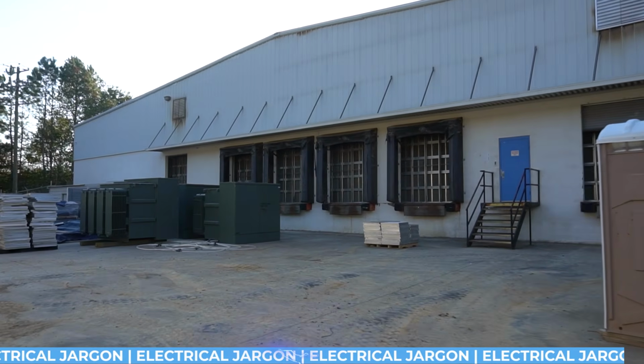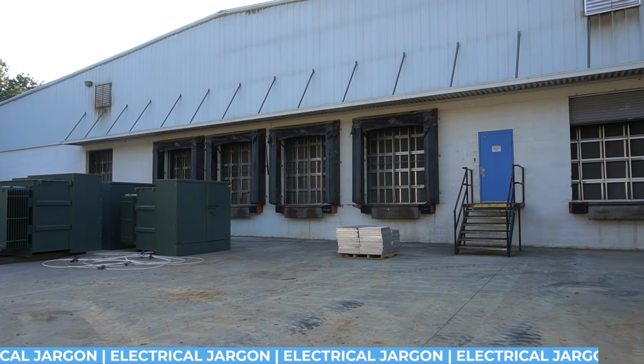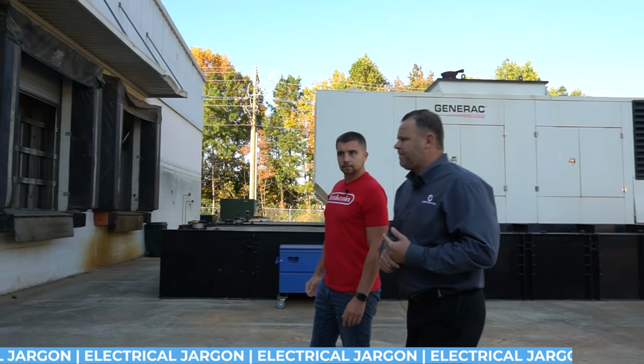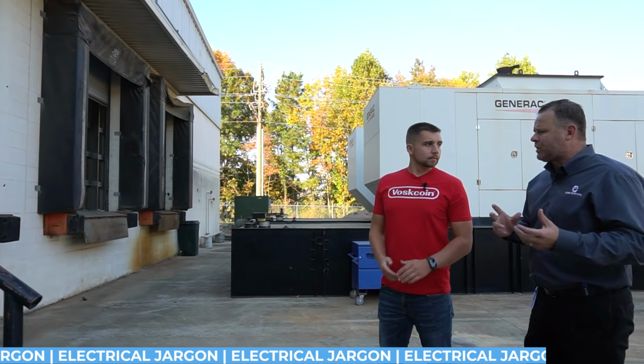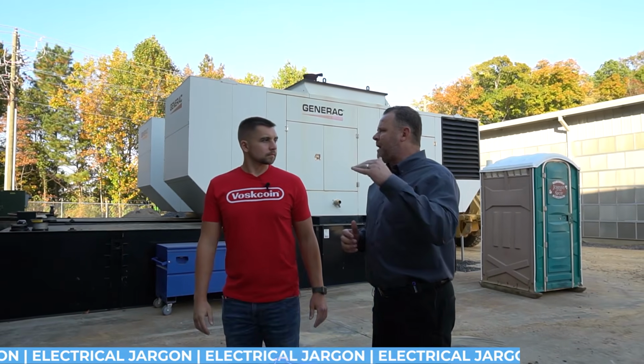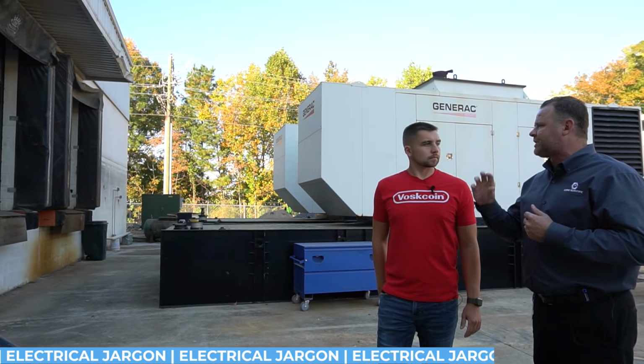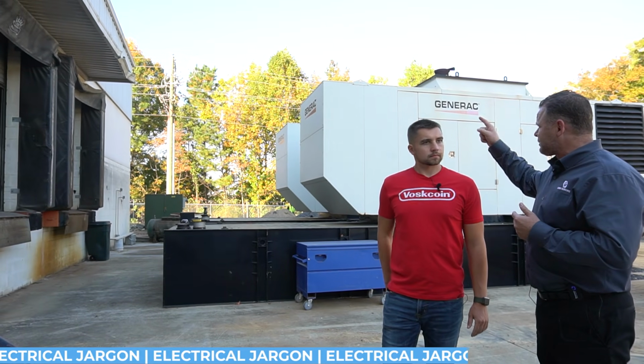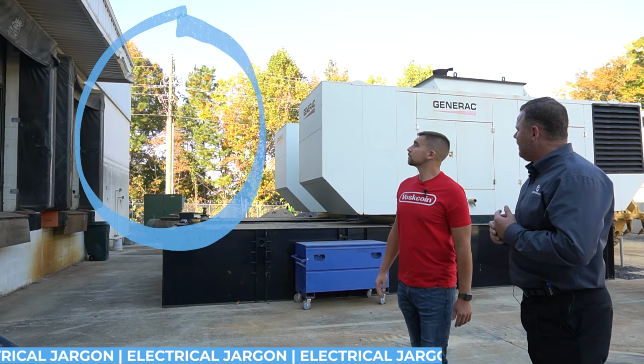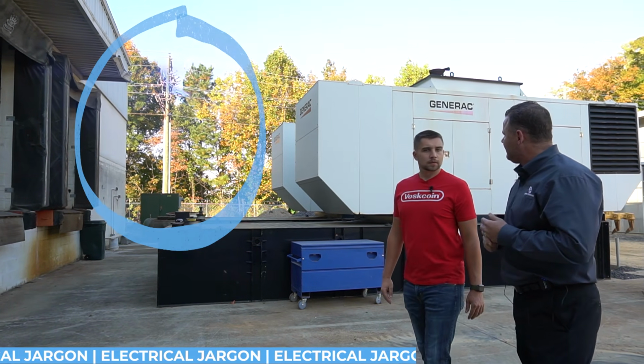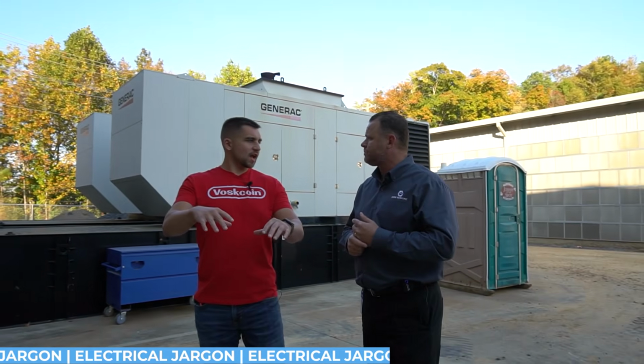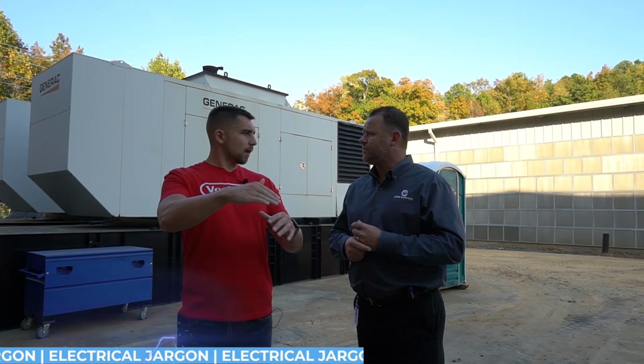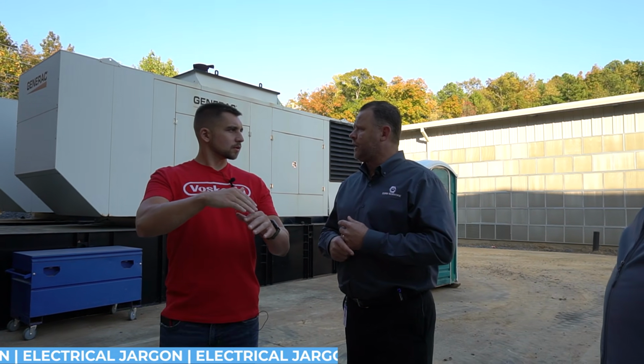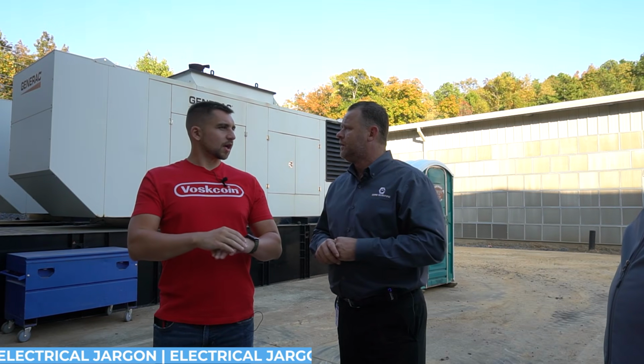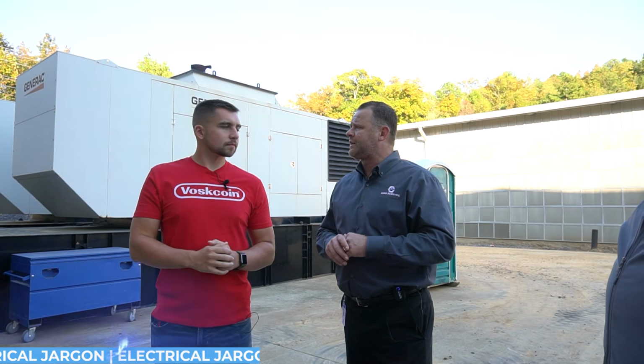All of our power here is 416, 240, 3-phase. We've dabbled with going to 277, but our master electrician elected to go with 416, 240, and it also is a unique voltage coming off of the poles here on the high voltage side. So it's 3-phase, so when you break it down, what are you getting at the miners? It's 240. So it's just a single phase of the 240. Okay, so when it hits at 240, it's not like 208 or whatever? That's right, it's 240 at the actual miner.